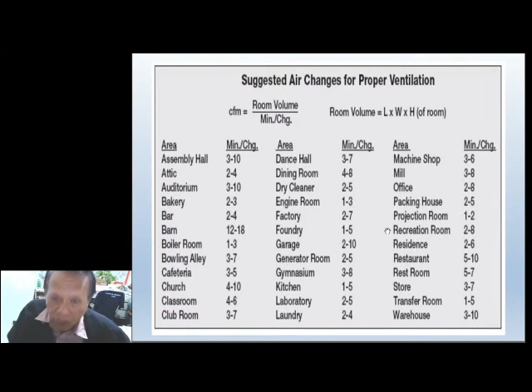Now, my suggestion is, this is quite a big range, no? How would you select? Now, since the Philippines is a hot country, meaning to say we are near the equator, so our weather or the ambient temperature is always much higher than in the northern hemisphere, in America, in Canada, and elsewhere in Europe, you know. So my suggestion is for you to use the higher value, no. Itong 3 is more doon sa kanila sa malalamig na lugar, and 10 is doon sa atin, no. So instead of 3, you use 7, okay, for this bowling alley, no. Projection room, 2 ang gamitin mo. Kung office, 8 ang gamitin mo. Okay? Minimum of air exchange. Okay?